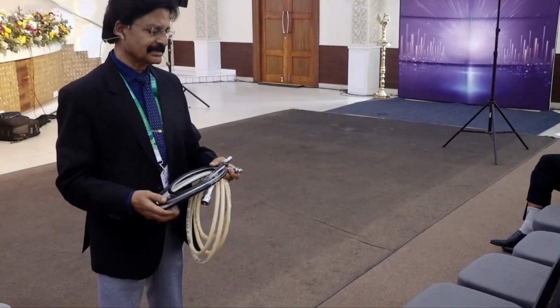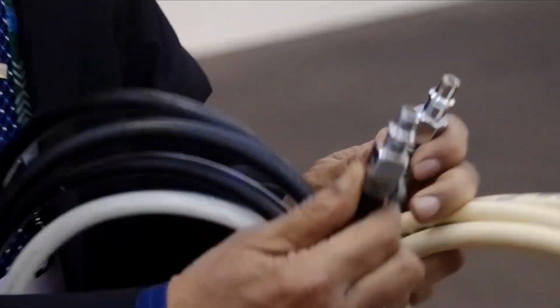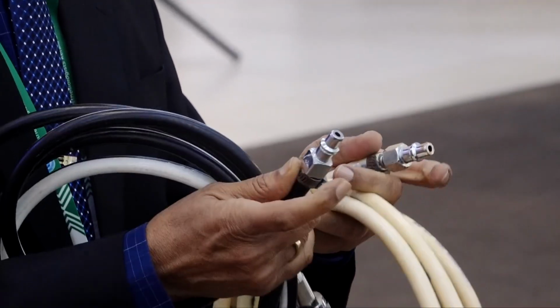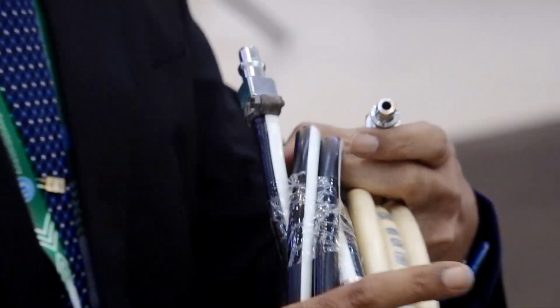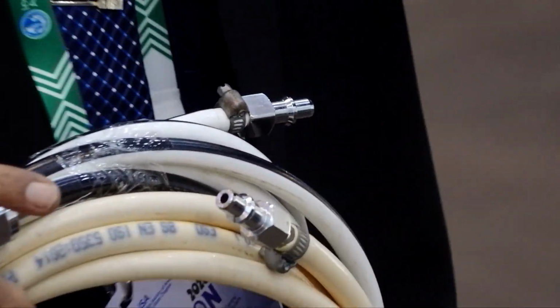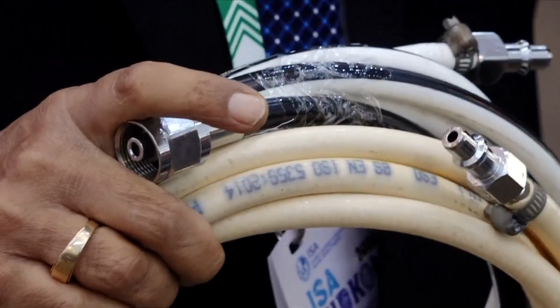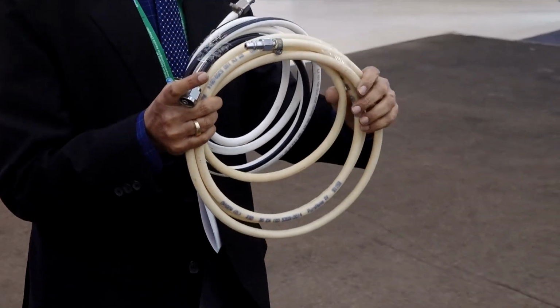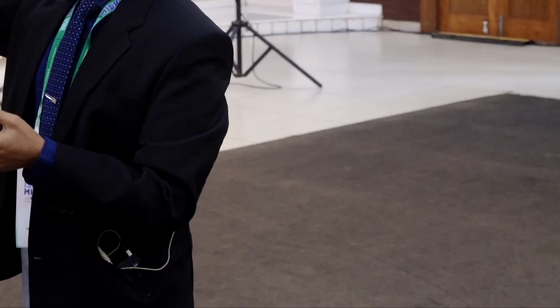And again, on the wall side also there are diameter indexes. These are at the wall outlet where you fix the oxygen and nitrous oxide and all these. So they also have a different kind of diameter index, but they are not called the diameter index safety system. They are called Schrader valves or quick couplers. Quick couplers, you can couple and uncouple quickly, but they are again diameter indexed and they are all color coded. You can just see the piping is also color coded. So that is about the diameter index safety system.